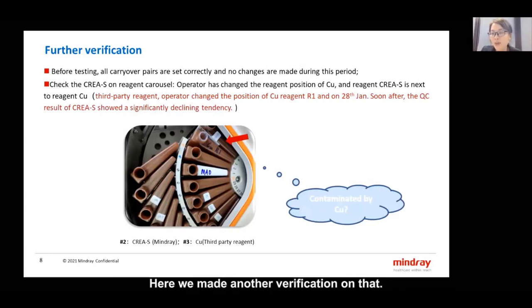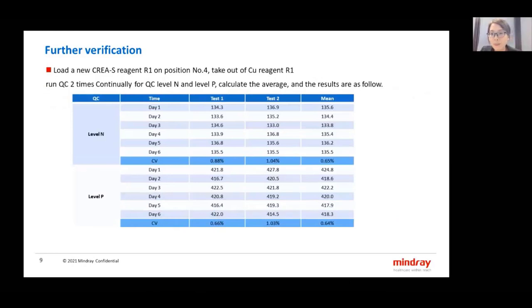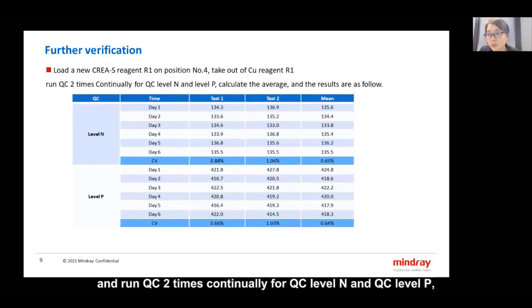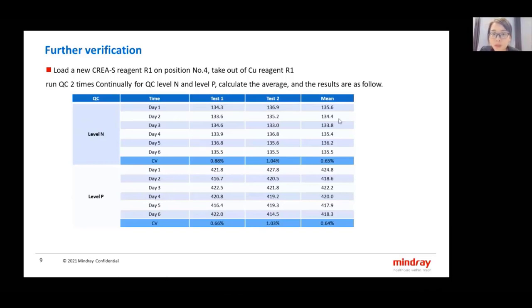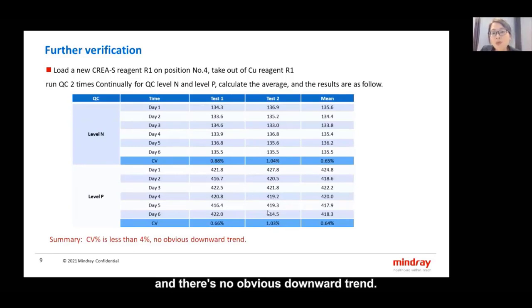Here we made another verification. We loaded a new creatinine reagent R1 on position number 4, and took out the Cu reagent R1, and ran QC 2 times continuously for QC level N and QC level P, calculated the average, and the results are as follows. As you can see, the CV is less than 4%, and there's no obvious downward change.